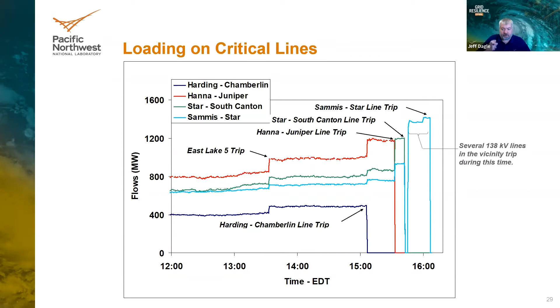But it took about an hour. That's kind of another key lesson of this. It took about an hour for the system to collapse, from when they really had a significant problem to when it had the uncontrolled cascading failure that took out the rest of the system. To me, that's remarkable, that the system would run for about an hour under those dangerous conditions. You always think of the grid as something you have to be right on top of, where things happen really fast, but sometimes it takes a long time for these problems to spiral out of control.